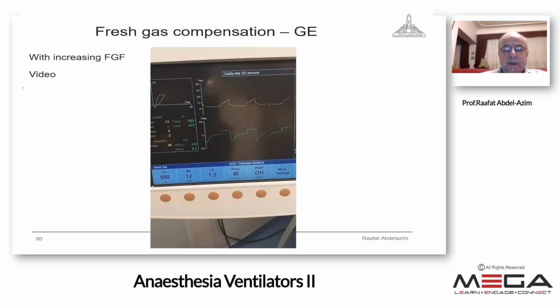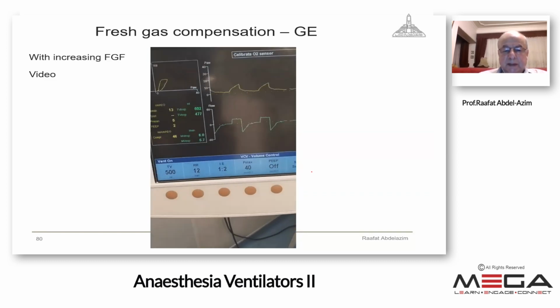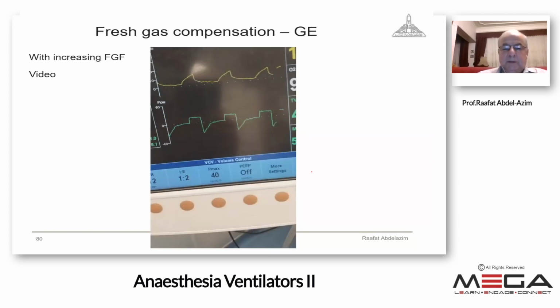The fresh gas compensation in General Electric ventilators will be explained in this video. We see the preset tidal volume of 500, and we will see the delivered tidal volume, which will be affected in the first few cycles by increasing. The delivered tidal volume will increase, but by activation of the fresh gas compensation after a few cycles, it will adjust the delivered volume to approximate the preset. You see now, the preset is 500, and the delivered is 480.